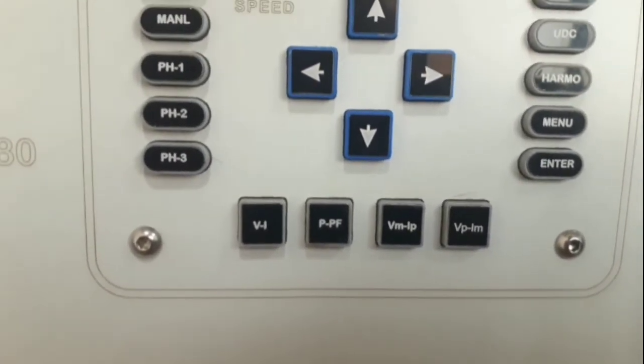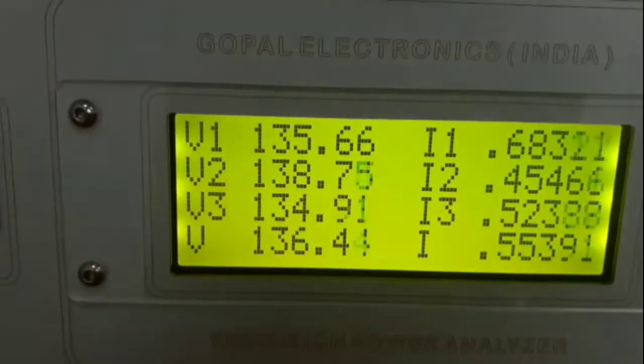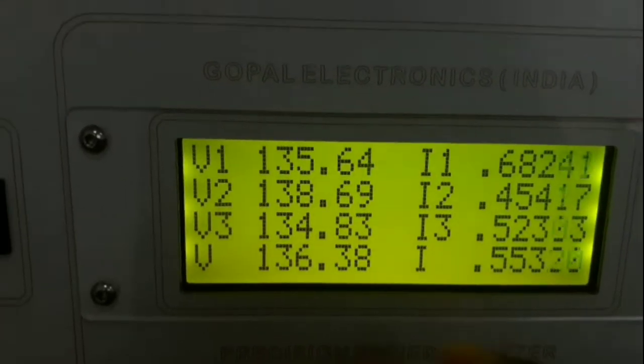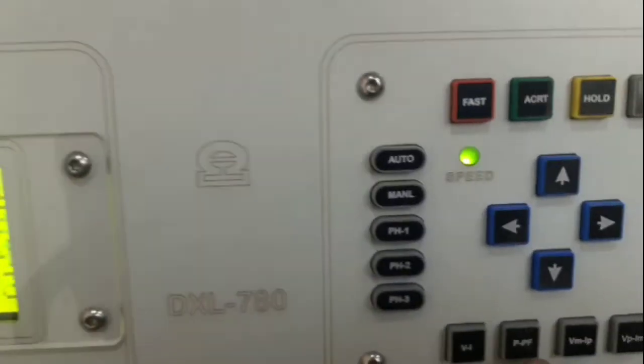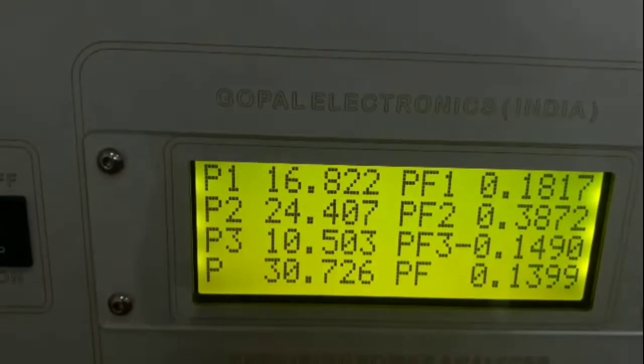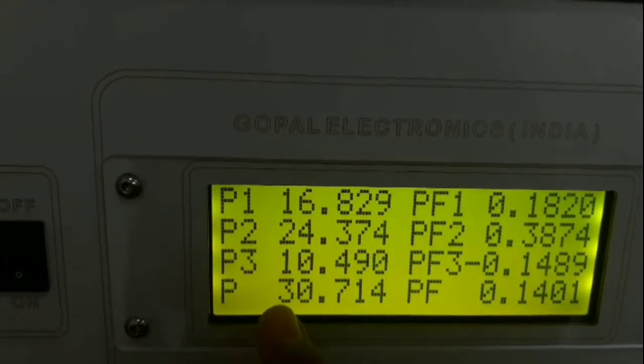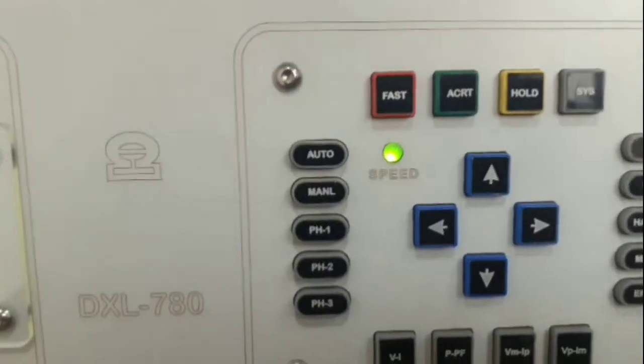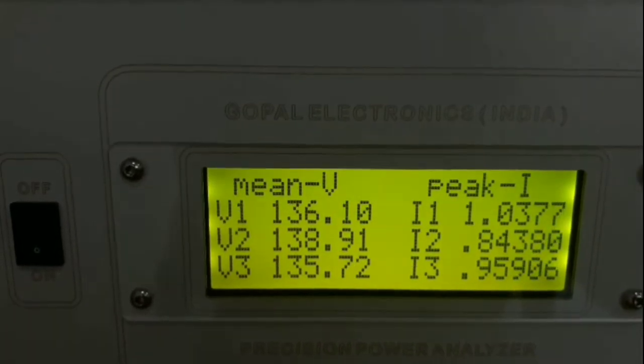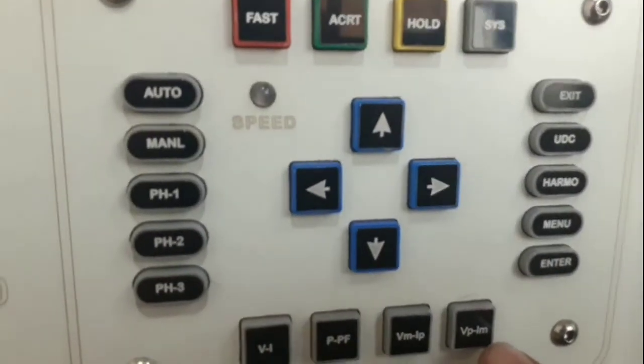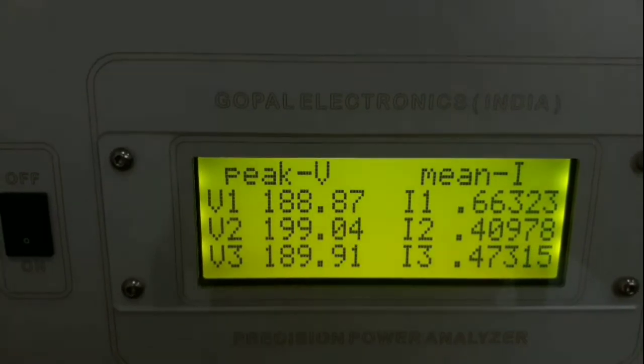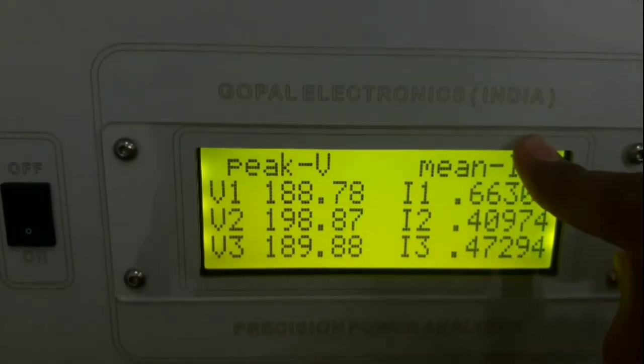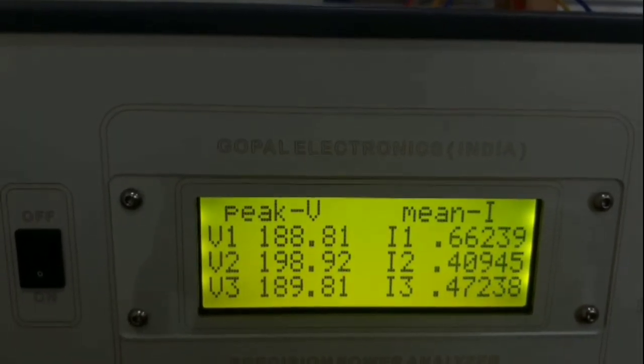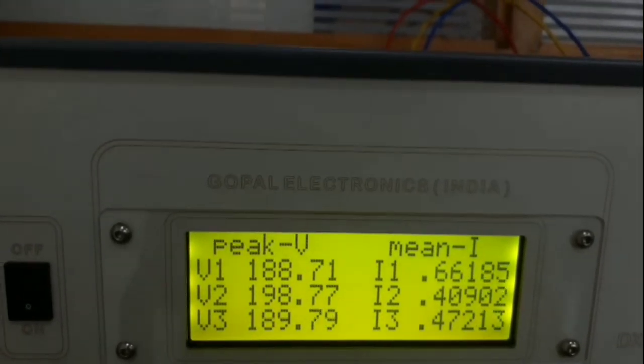You can see that here we have 4 different keys below. Press the first key, VI, and you can see all system voltage and current for all phases and the system. Now press the second key, PPF. Now you can see all phase powers and power factors, and system power and system power factor. Another key is V mean and I peak. You can see the mean value of voltage of all phases and the peak value of current of all phases. In the same way, the V peak and I mean key is given. By pressing this key, you can see the peak value of voltage of all phases and the mean value of current of all phases. So these were the functions of our power analyzer model DXL 780, and thanks for watching this video, friends.